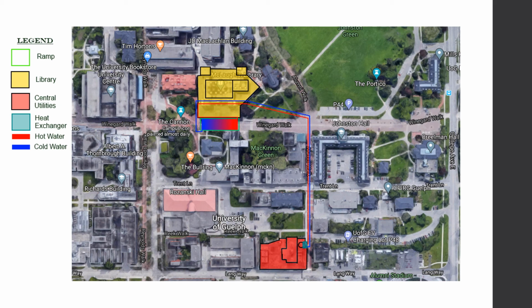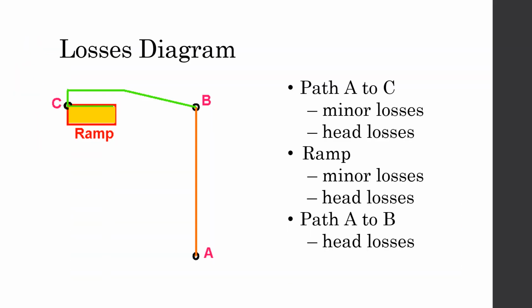Following this, the cold water will be returned back to the heat exchanger where it will be heated again for reuse in the system. The system will have losses in 3 separate sections. First, the friction and head losses at the bends, point A to point C on the diagram. Second, friction and head losses through the ramp setup at the ramp. And third, the head losses from point A to point B. These values total to about 313 meters, which is accounted for with the purchase of the pump for the system.